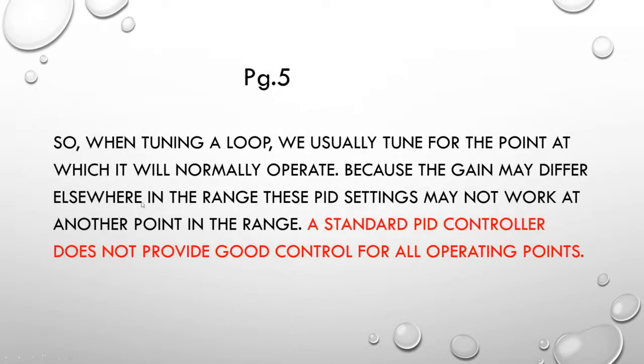When we're tuning a loop, we usually tune for the point where we'll normally be operating. Because that gain varies elsewhere in the range, the PID settings made at that operating point may not work at another point. Long story short, a standard PID controller does not provide good control for all operating points in a non-linear process, which we have defined as most processes.